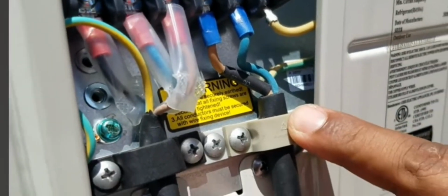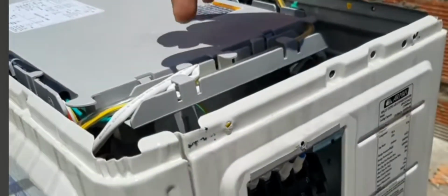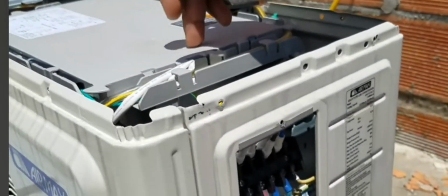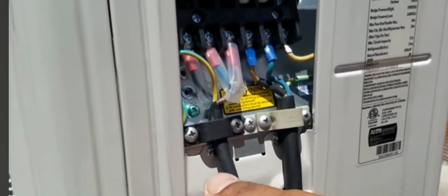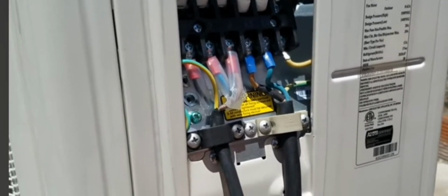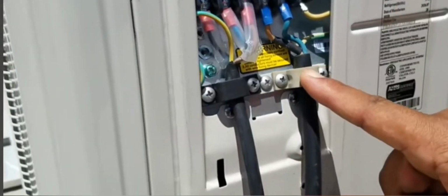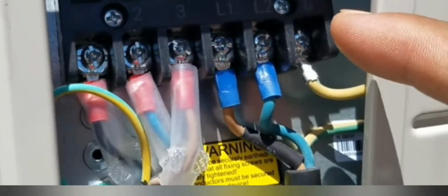Well, now to complete the explanation, we are going to see in the equipment already installed, you will see that there is a cable that energizes the outdoor unit card. Yes. This cable comes directly from the electrical connection. And then we have the intercommunication cable that we were talking about previously in the diagram. This cable is the one that carries the current and the signal toward the indoor unit. And this cable is the one that energizes the whole equipment and has L1, neutral and ground.